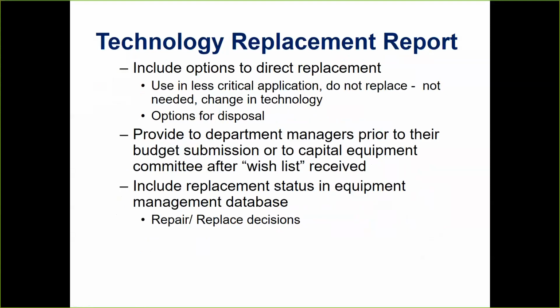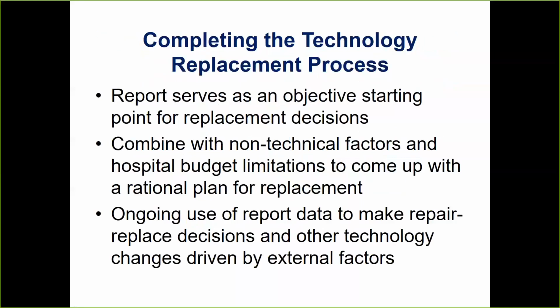There may be options to redirect replacement, use in a less critical application. For example, a defibrillator that's used in an emergency department could perhaps, even though it's fairly new, you're concerned because of the high risk, but it still may be serviceable. That may be utilized in, say, obstetrics. So we tried to provide, in the hospital setting, a report to department managers prior to their budget submission and review that with them, looking at the replacement status. So it's an objective, quantitative starting point for replacing technology.